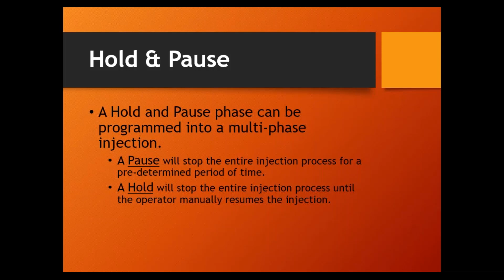Now, a pause is the same thing, but for a predetermined length of time. But if I wanted to program a pause in phase 2, I would have to program pause and then say for 10 seconds, 5 seconds, whatever. Then what happens is if I shoot that shot, we get to phase 2, it pauses, the little counter starts counting down, 5, 3, 2, 1. Then when it hits 0, automatically starts shooting it. The operator does not have to reinitiate. Now it's a subtle difference between a hold and a pause, but that's the difference between it.